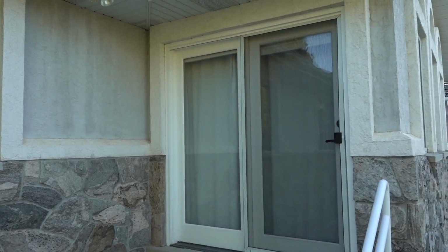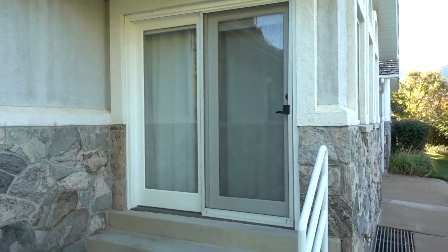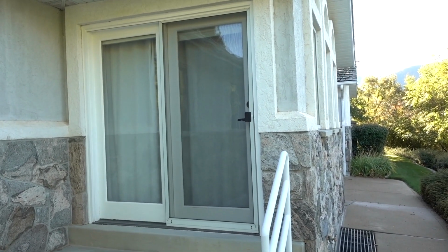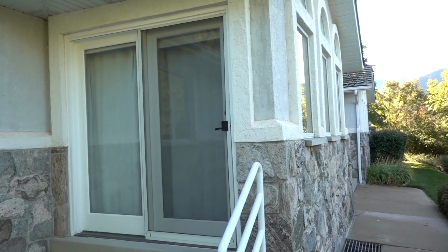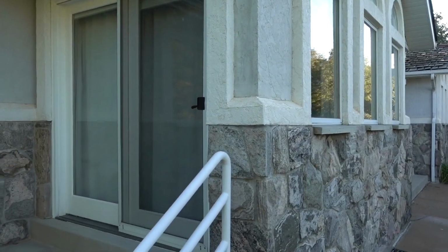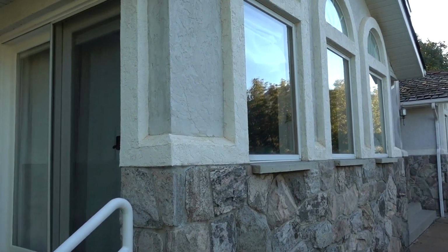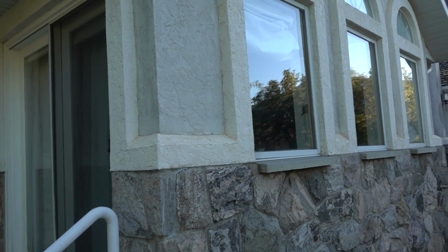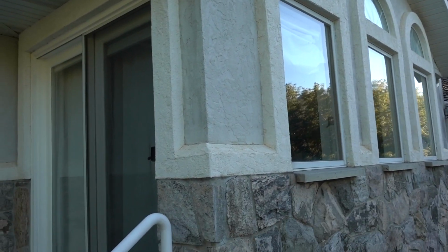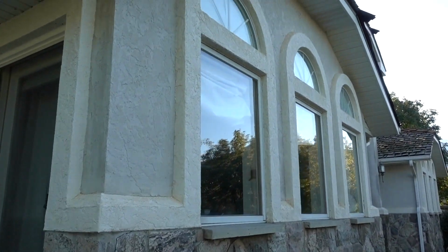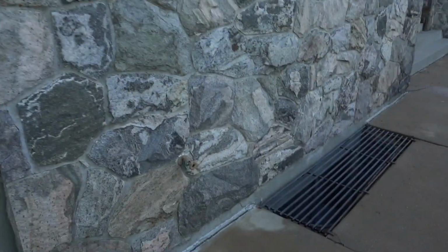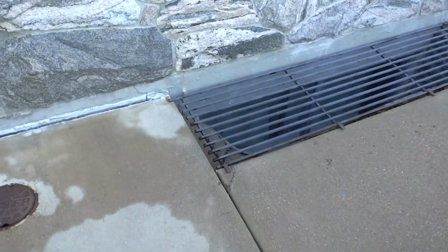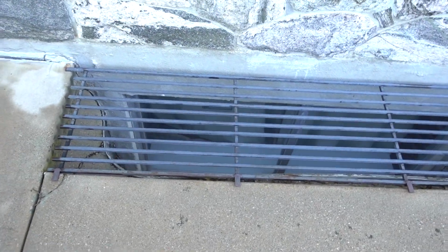And so we're going to go through, and I'm going to film that, and I'm going to try to pause the film in post and see if I can put some dimensions on there so that we can run the loads. By the way, I'm standing on the west side of the house. That's important when it comes to heat load calculations, and we'll just film everything that I'm going to be putting dimensions to later.